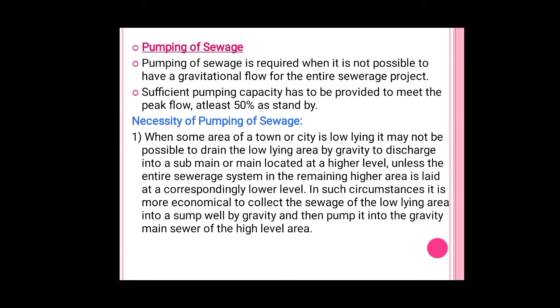The next concept is the pumping of sewage. The pumping of sewage is required when it is not possible to have a gravitational flow for the entire sewage project. Sufficient pumping capacity has to be provided to meet the peak flow, with at least 50% as standby. So first of all we see what is the necessity of the pumping of sewage.